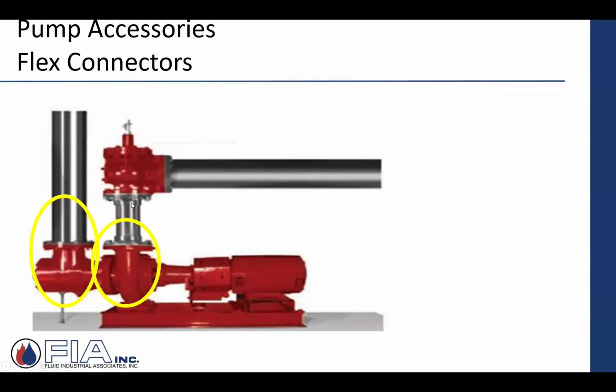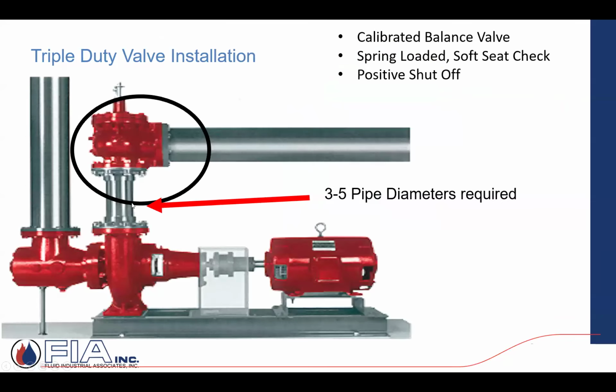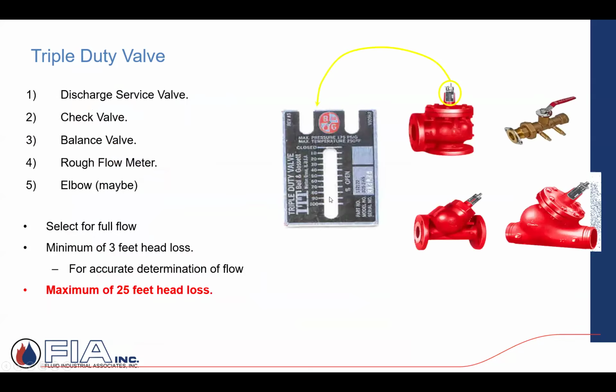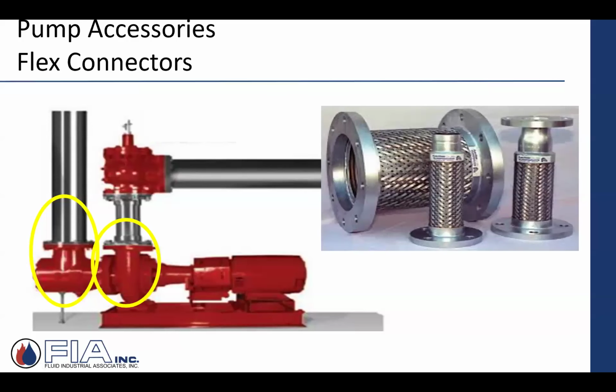And there was a screen back here that talked about typically, from the discharge of that pump before we get to that triple duty valve, they're looking for a minimum of around 3 pipe diameters. They could use that flex pipe to fill that gap, as well as, again, alignment, just lining up from the discharge of the pump to the triple duty valve.